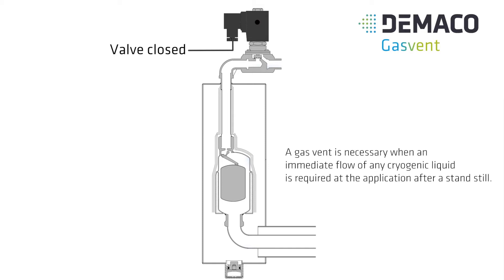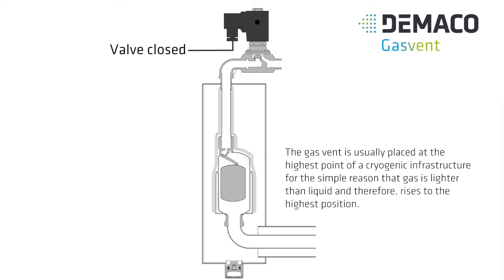A gas vent is necessary when an immediate flow of any cryogenic liquid is required at the application after a standstill. The gas vent is usually placed at the highest point of a cryogenic infrastructure for the simple reason that gas is lighter than liquid and therefore rises to the highest position.